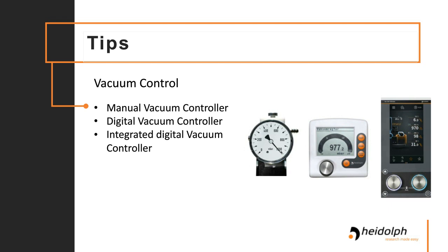There are a couple of different methods of controlling your vacuum. The first, and usually the cheapest, is a manual vacuum controller — a gauge where you can see what the vacuum is, then leak it a little to keep it at the parameter you want.